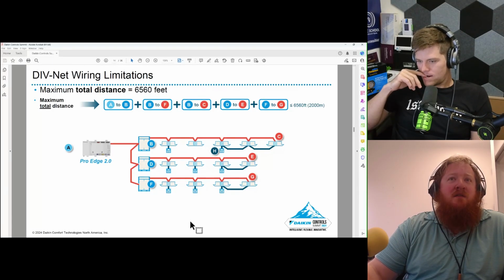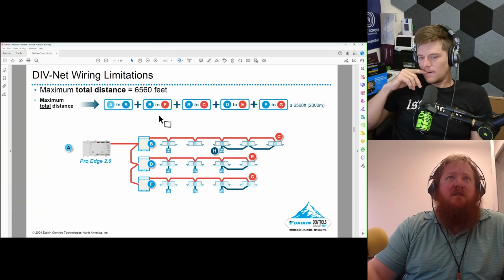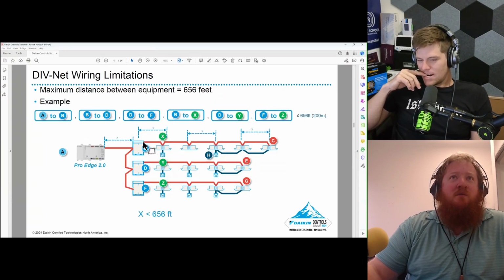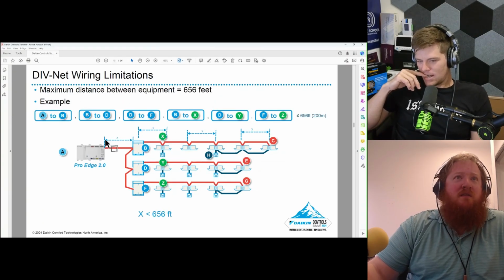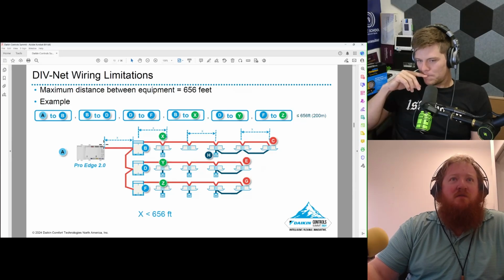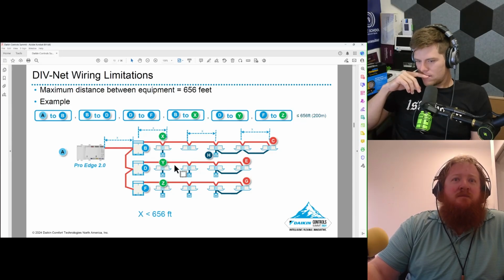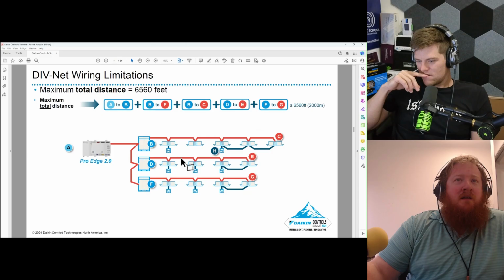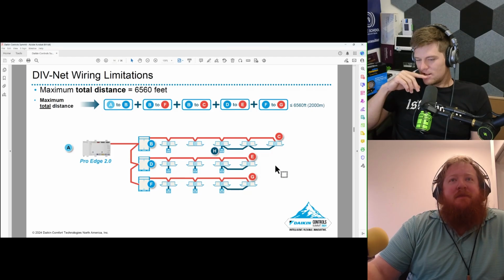Previously that was 3200, right? So it looks like it's doubled. But as long as we're not breaking this rule, this 656 feet between devices, technically it looks like we're getting double the amount of wiring. Now I want to run it at 657 feet and see what happens.